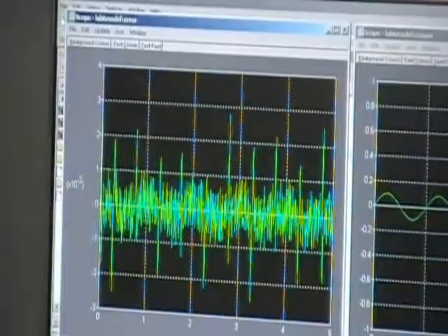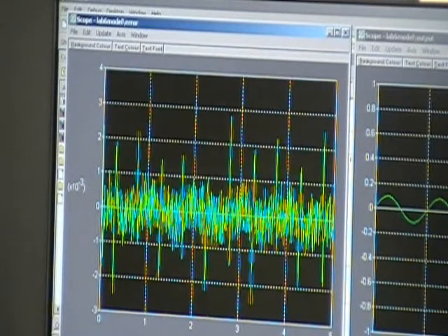And also, you should test it at about 2 frequencies. So we'll do it at about say 3 hertz. Yep. The reason I suggest you do 3 or 2 hertz and not 5 hertz is because in my experience, these motors at 5 hertz, some damage happens to the gearbox due to excessive chattering. So it's not really a good idea to damage stuff. So he'll just show you one with the same poles at 3 hertz. 3 hertz? Yeah.